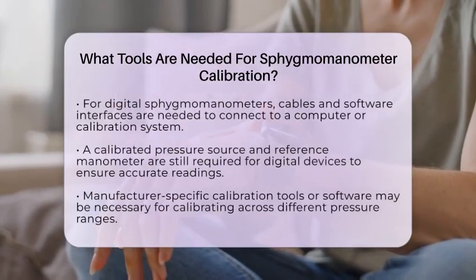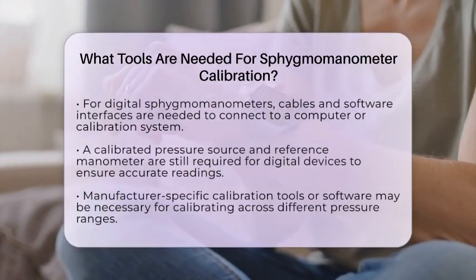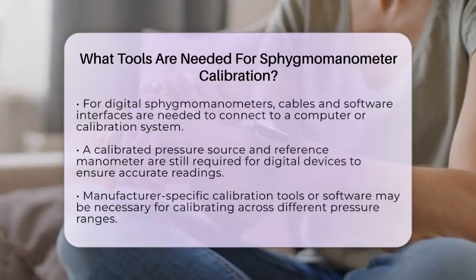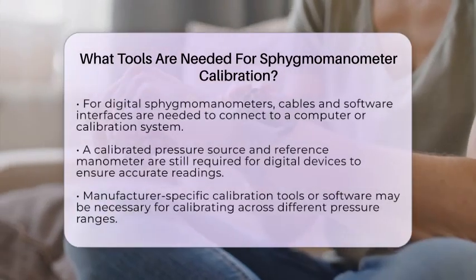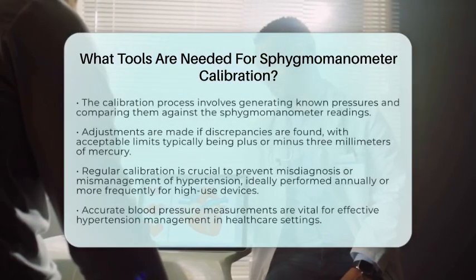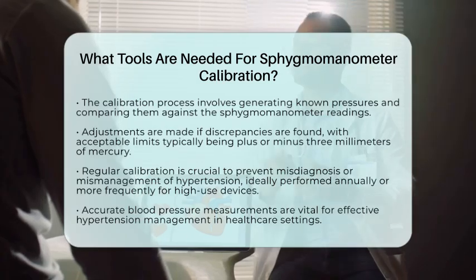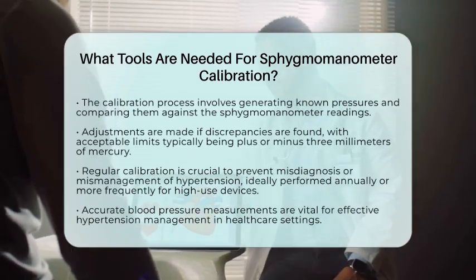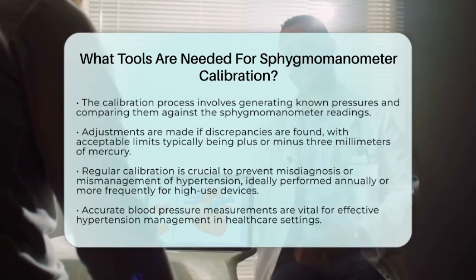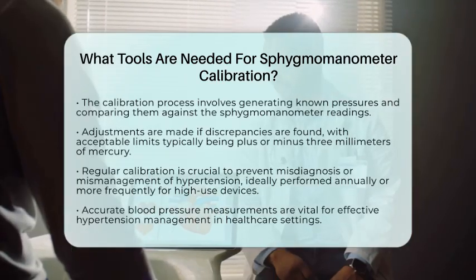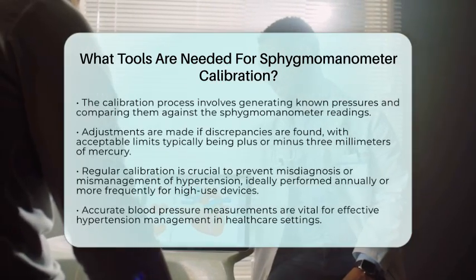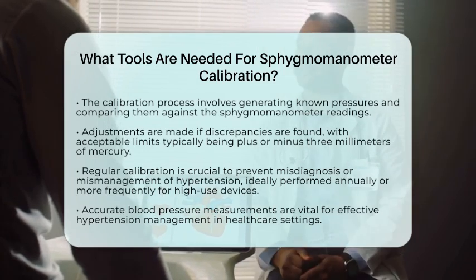The calibration process itself involves generating known pressures and comparing the sphygmomanometer readings against the reference standard. If there are discrepancies, adjustments are made or correction factors noted to ensure measurement errors remain within acceptable limits, typically plus or minus 3 millimeters of mercury or better.